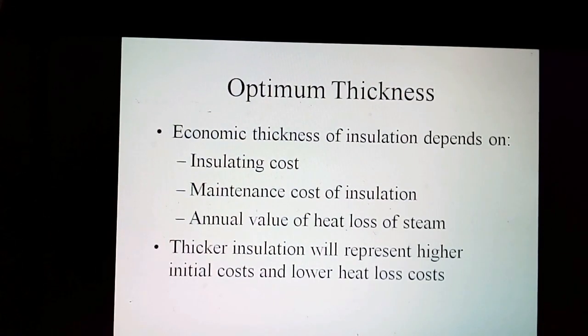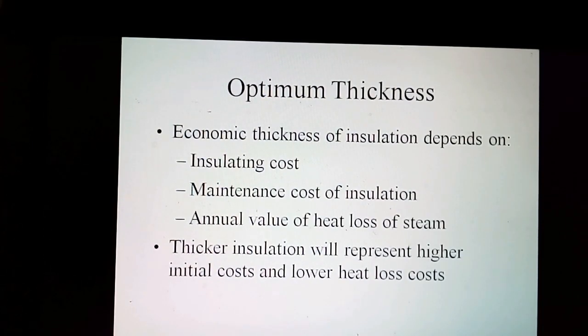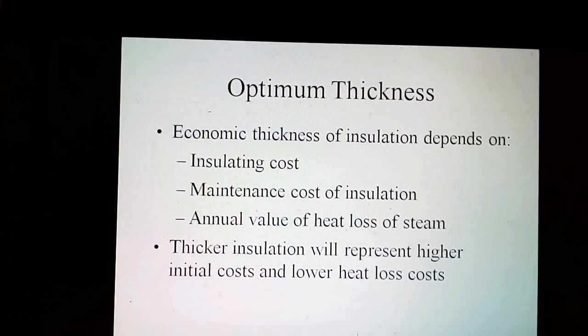Optimum thickness for pipe: The economic thickness of insulation depends on the first cost, installation cost, and maintenance cost of insulation, and the annual value of heat loss, which depends on the cost of producing the steam and the thermal conductivity of the lagging. Generally, thicker insulation will represent higher installation costs and lower heat loss costs.